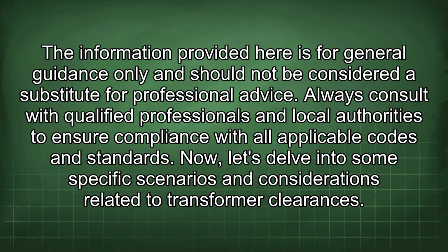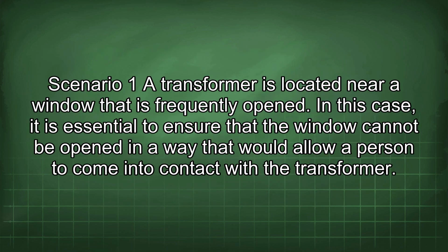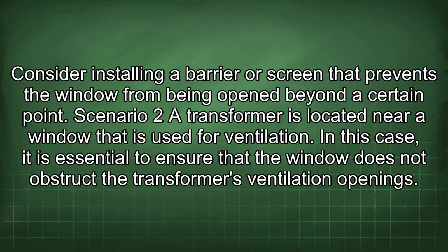Now, let's delve into some specific scenarios and considerations related to transformer clearances. Scenario 1: a transformer is located near a window that is frequently opened. In this case, it is essential to ensure that the window cannot be opened in a way that would allow a person to come into contact with the transformer. Consider installing a barrier or screen that prevents the window from being opened beyond a certain point.